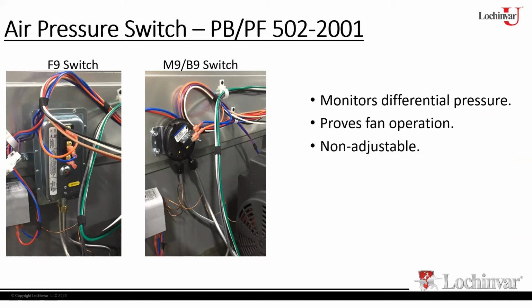Now, for the F9 model, however, that's why you see the F9 switch there. For the F9 model, it's a positive pressure system. In this case, if you energize the valves, they're going to open and they're going to dump gas in, whether the fan's running or not. So I have to have some way to prove that the fan's operating. So we're going to use a low air switch. All right? A low air pressure switch is a normally open set of contacts. So it takes a pressure increase on the fan side to make the switch.